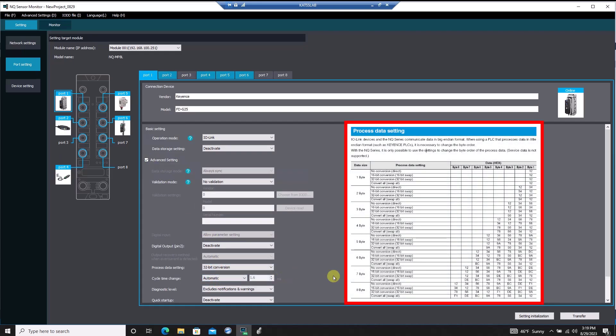So far we've covered implicit messaging, which updates cyclically between the NQ and the PLC, but there is more information that can be accessed via explicit messaging, which is a one-time message that requires a trigger. Explicit messaging is used to access IO-Link service data, which allows reading and writing of the sensor settings and execution of commands, such as tuning. An example where I'd want to send a write request to a parameter is to reset the accumulation of airflow on a flow meter.